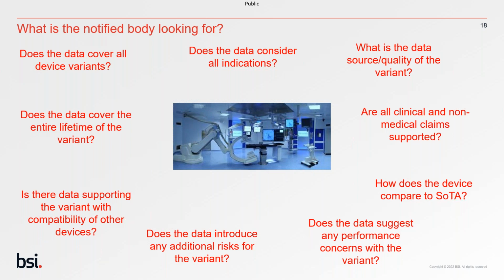What is that actual data source and quality of that data source for that particular variant? Does that variant of maybe 100 devices, is there enough to cover the lifetime? Has that been picked up in post-market clinical follow-up? Really, you can see the amount of questions that we're looking at, and we have to look for each variant and make sure that's called out to us as notified bodies as part of the clinical evaluation assessment report, really to make sure that you have sufficient data for all variants and sizes. So these are the questions that we have to ask ourselves.